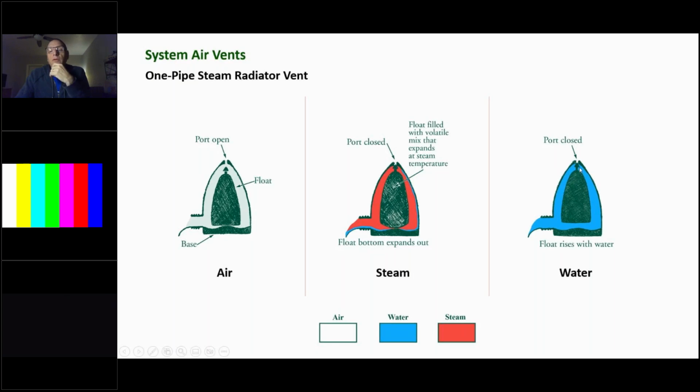So it will stay closed until the water drops below the vent, and then it will reopen back to the first page. What's kind of important about these valves is that, let's go with the 1A valve, if you look at the literature, the box, or the vent itself, the 1A vent has a maximum 10 psi operating pressure.